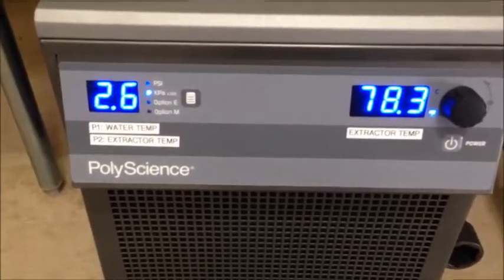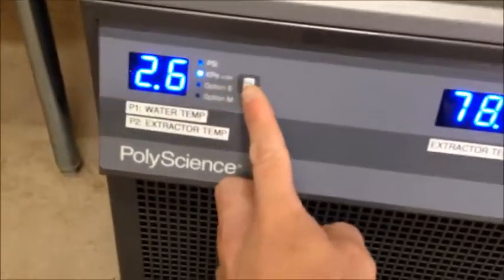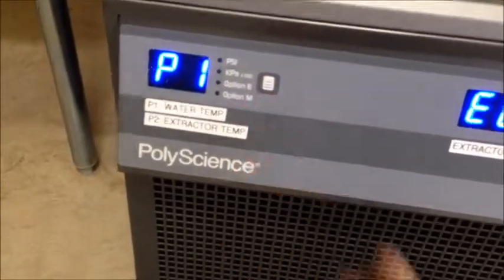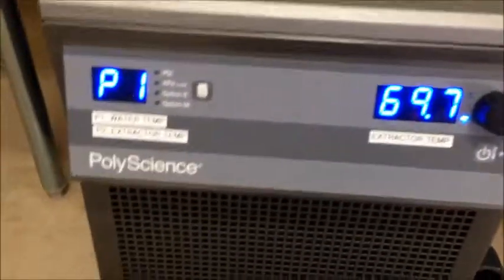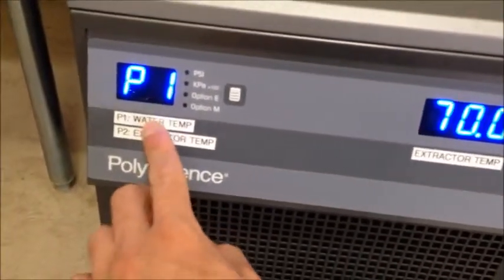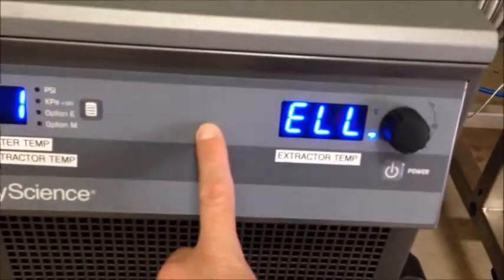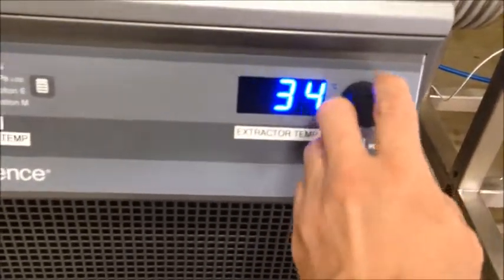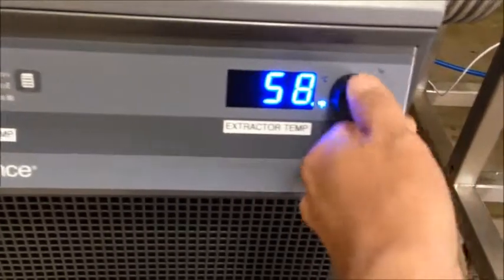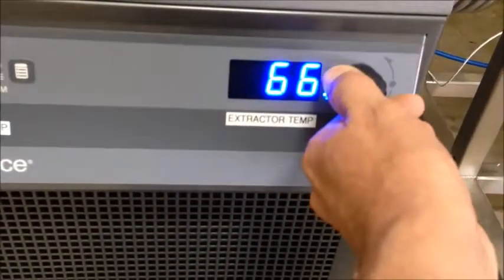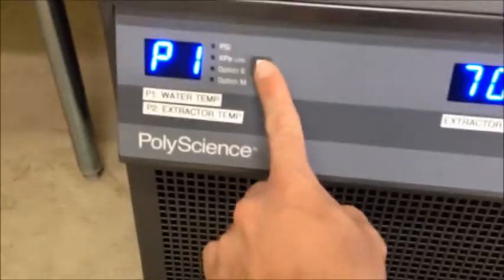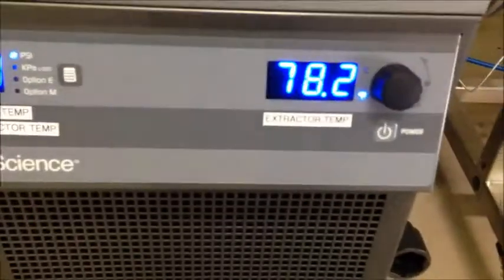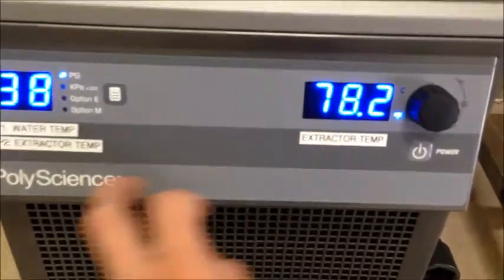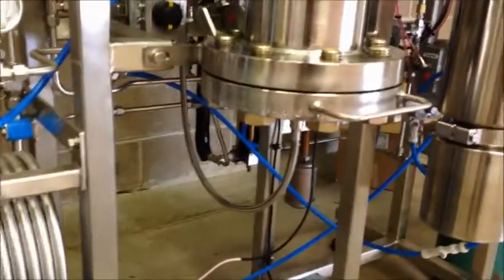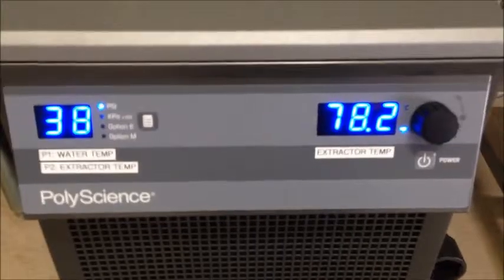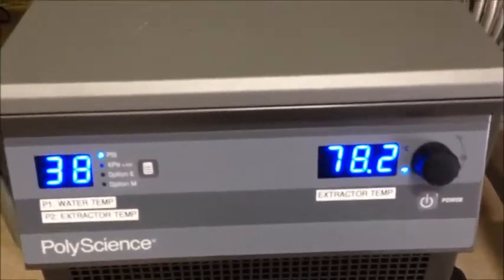There it goes. Now to check to make sure it's reading the remote temperature probe, you scroll through here. And as long as a P1 pops up, that means that you're reading the remote temperature probe. So P1, when you have it on P1, you're seeing what the water temperature is inside of here right now. If you're not seeing the P1, so like right here, now you're actually reading over here what P2 is, the extractor temp. So on the 1-liter system, it's the exact same way. You'll just be reading what the extractor temp is on the 1-liter system.